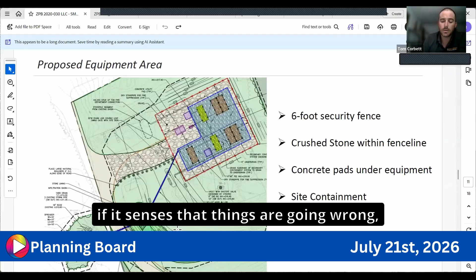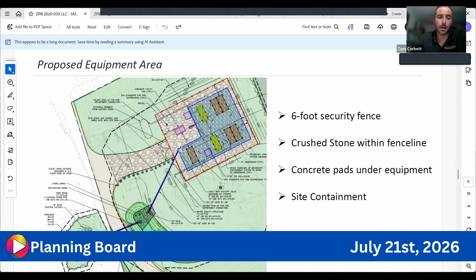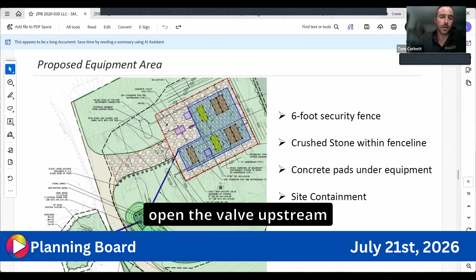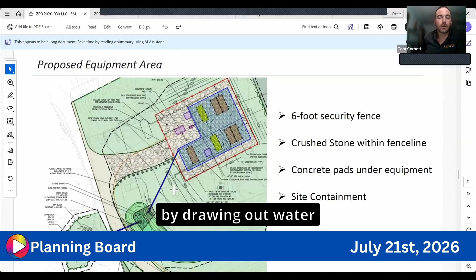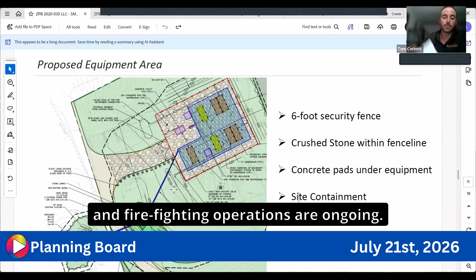The purpose of that is, in a worst case scenario - which we plan for with every site we work with - if 17,000 gallons happens to not be enough water capacity, which is highly unlikely, we have the ability to close the downstream valve, open the valve upstream of the water quality unit, and pump water out to increase that volume capacity while firefighting operations are ongoing.